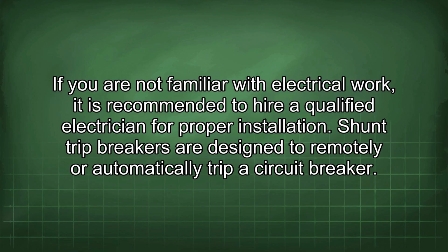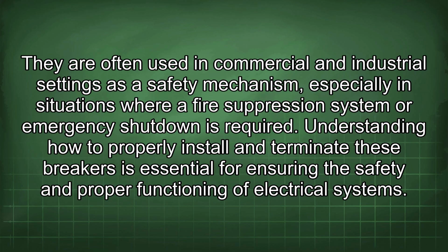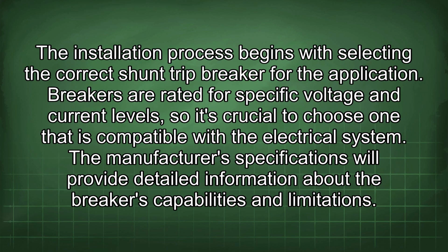Shunt trip breakers are designed to remotely or automatically trip a circuit breaker. They are often used in commercial and industrial settings as a safety mechanism, especially in situations where a fire suppression system or emergency shutdown is required. Understanding how to properly install and terminate these breakers is essential for ensuring the safety and proper functioning of electrical systems. The installation process begins with selecting the correct shunt trip breaker for the application.